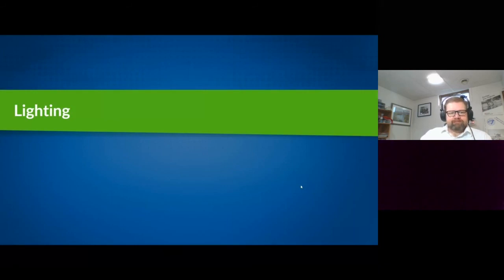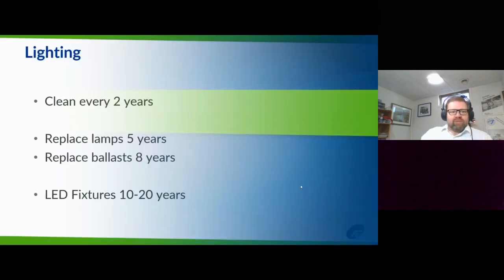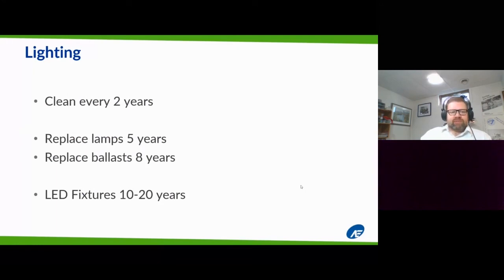While I have your ears, lighting is something that's usually forgotten. You should be cleaning it every 2 years, and no one does. You should be replacing lamps, if they're not LED, every 5 years, no one does. And you should be replacing ballasts every 8 years, again no one does. Because you don't do any of these things, everything's quite dim. Then someone comes along, throws some LEDs in, and you find the room is twice as bright. That's because your existing system had old lamps, old ballasts, and they were dirty.